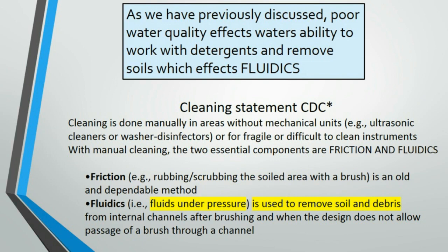And it's used to remove soil and debris from internal channels after brushing and when the design does not allow for passage. So if we're talking about, say, something from Intuitive, where there are long lumens inside those devices that you can't put a brush through. It is not recommended. So if you have those, I'm sure you're familiar with the IFU and just how much flushing or just how much fluidics is used to get those items clean.